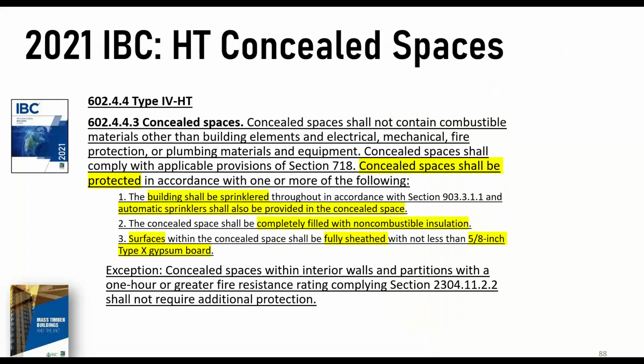So if you're going to have exposed wood, it needs to be protected. And there's very detailed provisions in the IBC. Again, this is just an introduction, so we're not going to get into it too heavy, but we have provisions for type 4 heavy timber. You can start to accommodate concealed spaces in the type 4 heavy timber. Again, the traditional heavy timber construction, 6 stories up to 85 feet, has to be fully sprinklered with an NFPA 13 system, and those automatic sprinkler systems have to provide protection for those concealed spaces.